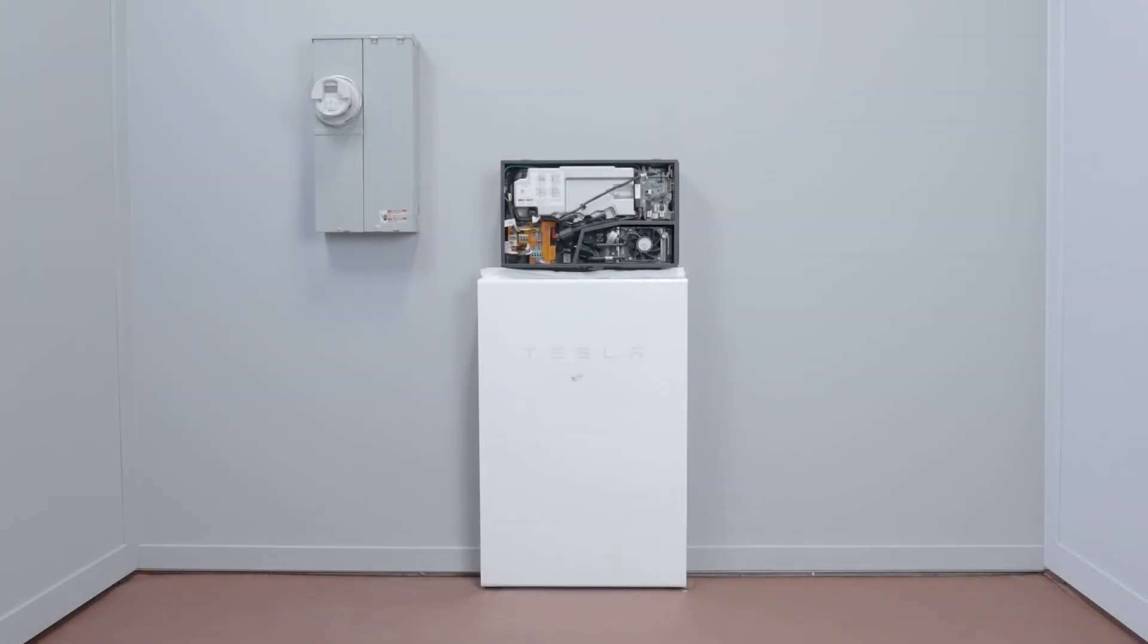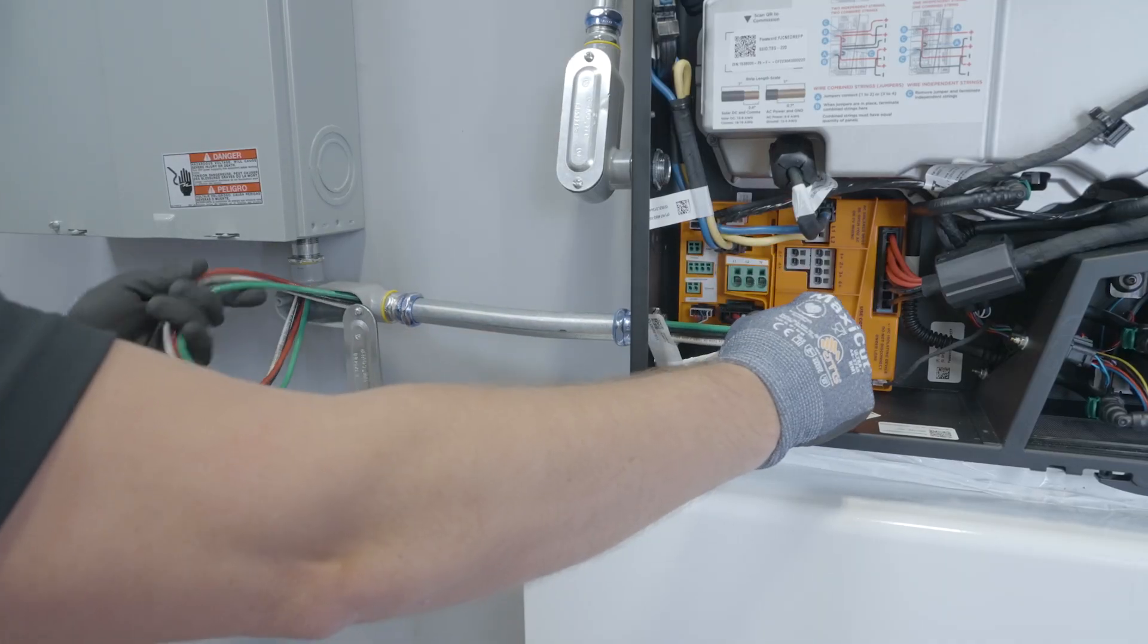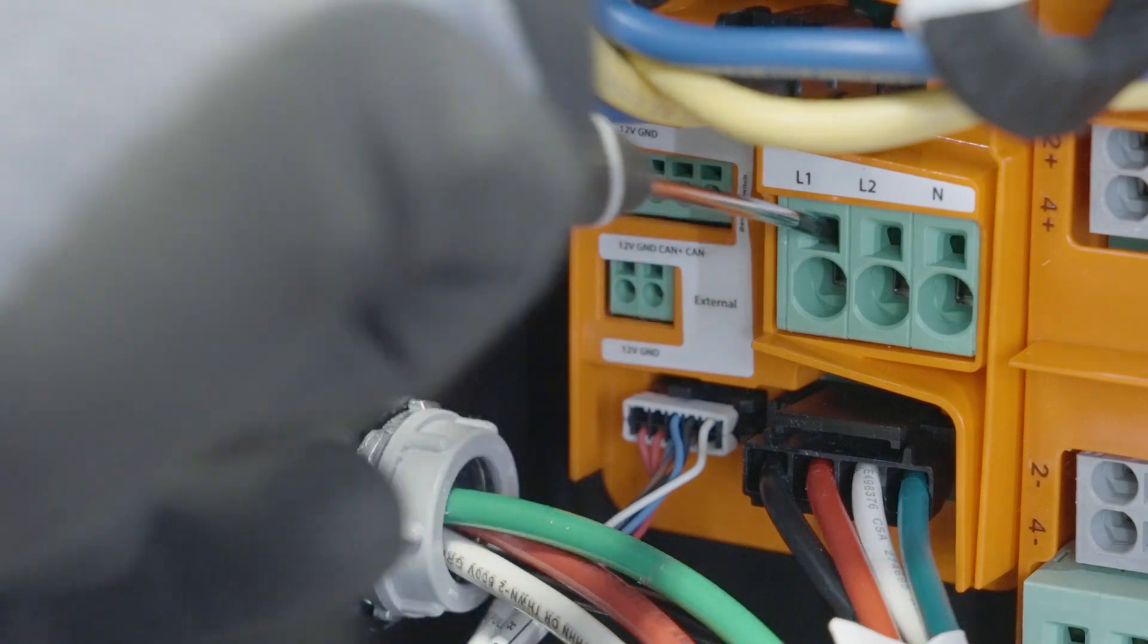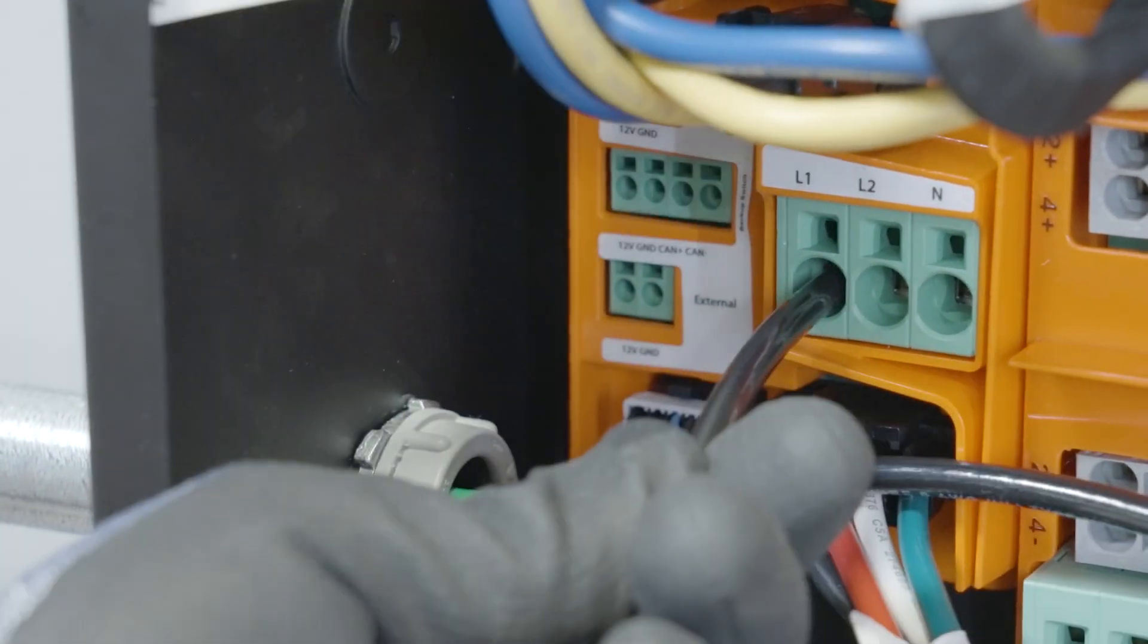Powerwall Plus is normally interconnected with a 50-amp two-pole breaker. This typically requires the use of number eight conductors. Strip half an inch of insulation from each AC conductor. Insert a cabinet-tip flathead screwdriver into the rectangular hole. This will open the adjacent circular terminal to receive the AC conductors.